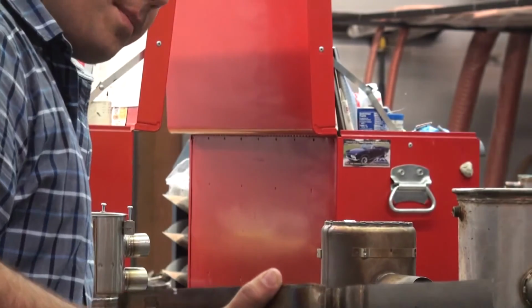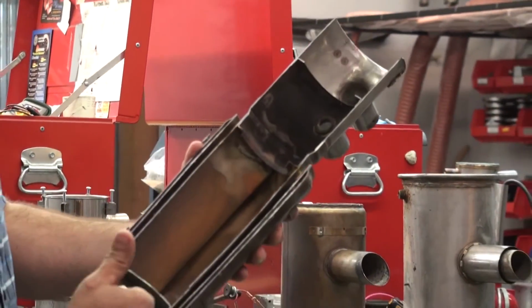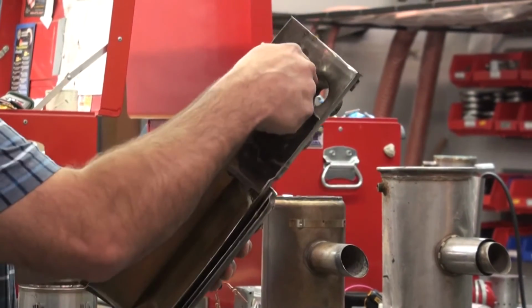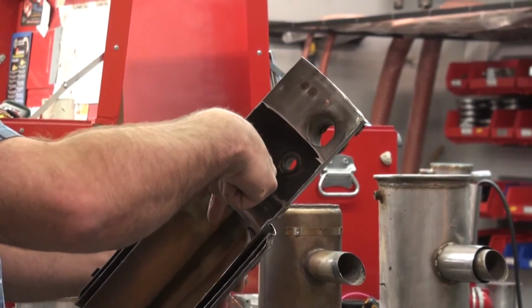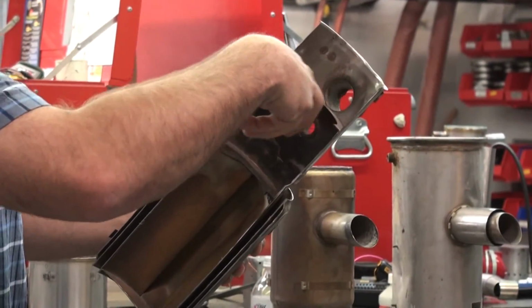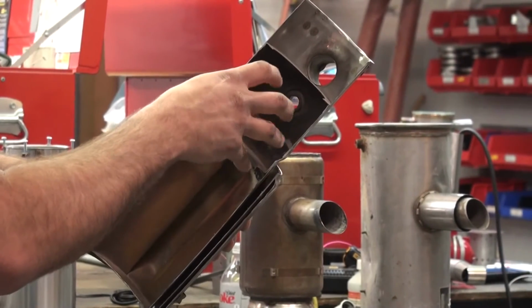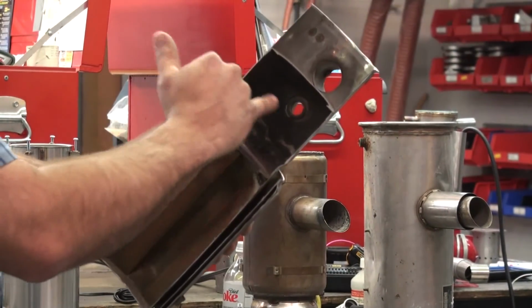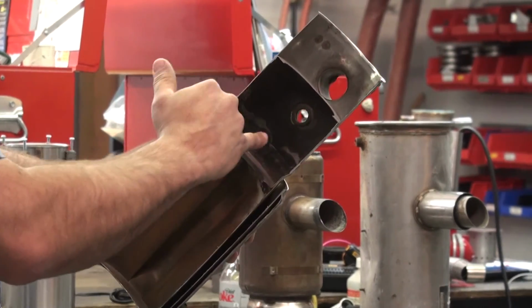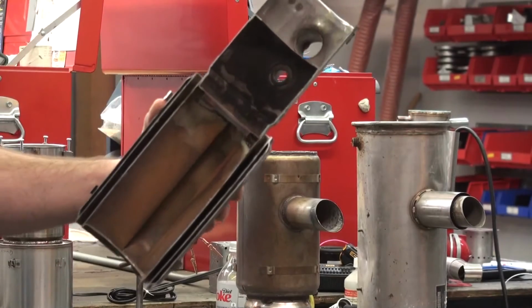And this one shows the cross-section of the actual crossover for the combustion tube. So air comes in here, here's the spark plug, air comes in, shoots straight down, hits the spark, the fuel hits the spark here, the fuel is atomized, so it creates the burn. Most of the burn happens down in this portion. You see a lot of carbon buildup in here. It's because you really don't have a burn up here in the mixer area. The burn is happening down in the burn chamber.